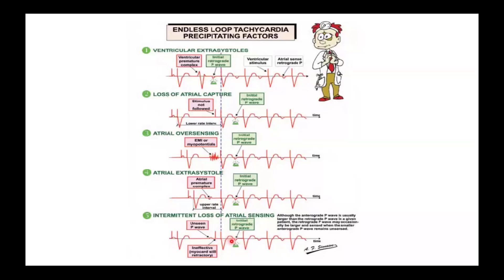Also, if there is intermittent loss of atrial sensing, as in the previous example, and there is no conduction, the atrial pacing spike is delivered after an unseen P wave. So the atrium actually is not captured. So there is a lot of time to allow for recovery of the atrium, and retrograde conduction occurs and the PMT starts. To overcome this, as Dr. Amir said, we can prolong the PVARP. Also adjust the sensitivity levels if there is undersensing of the retrograde P wave, which means that we make it less sensitive.